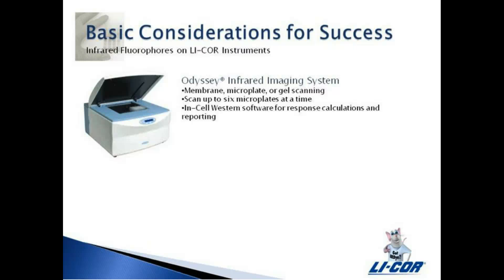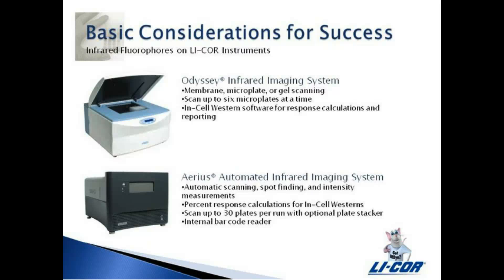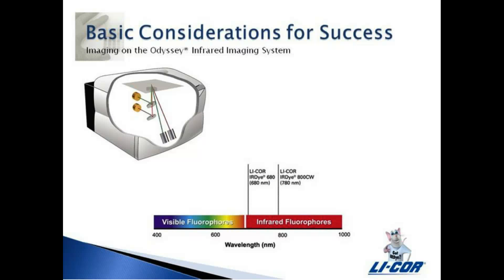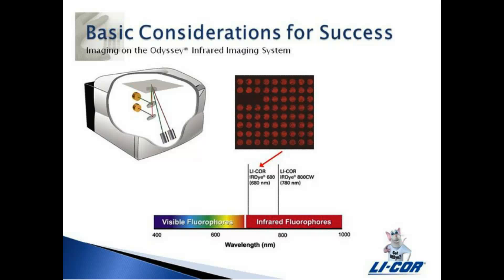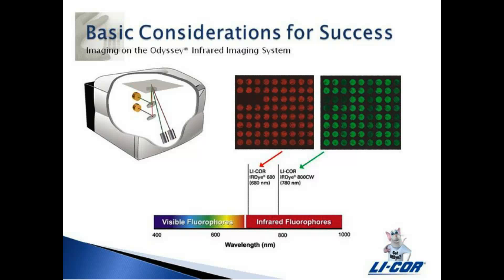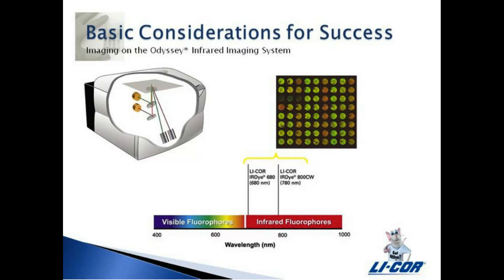In-cell westerns assayed with the infrared fluorophores on the Odyssey Infrared Imager or the Aerius Automated Infrared Imaging System are capable of simultaneously detecting two targets using two spectrally distinct dyes. Separate lasers and fluorescence detectors are used for each dye. IRDye 680 emits at approximately 700 nanometers and IRDye 800CW at approximately 800 nanometers. The images can be viewed separately or overlaid.